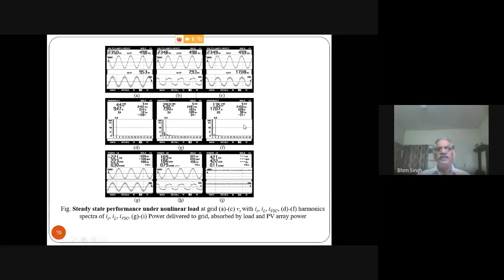The major reason for this is that it's not only generating the harmonic the load needs, it's also taking active power which goes to the grid. You can see the power going to the grid is around 2.21 kilowatts, while the power generation from solar is 4.21 kilowatts, and that much power is consumed by the load. So the remaining power, after losses, goes to the grid. It works as solar power generation as well as an active filter, and it will continue working as an active filter irrespective of how much solar generation there is.